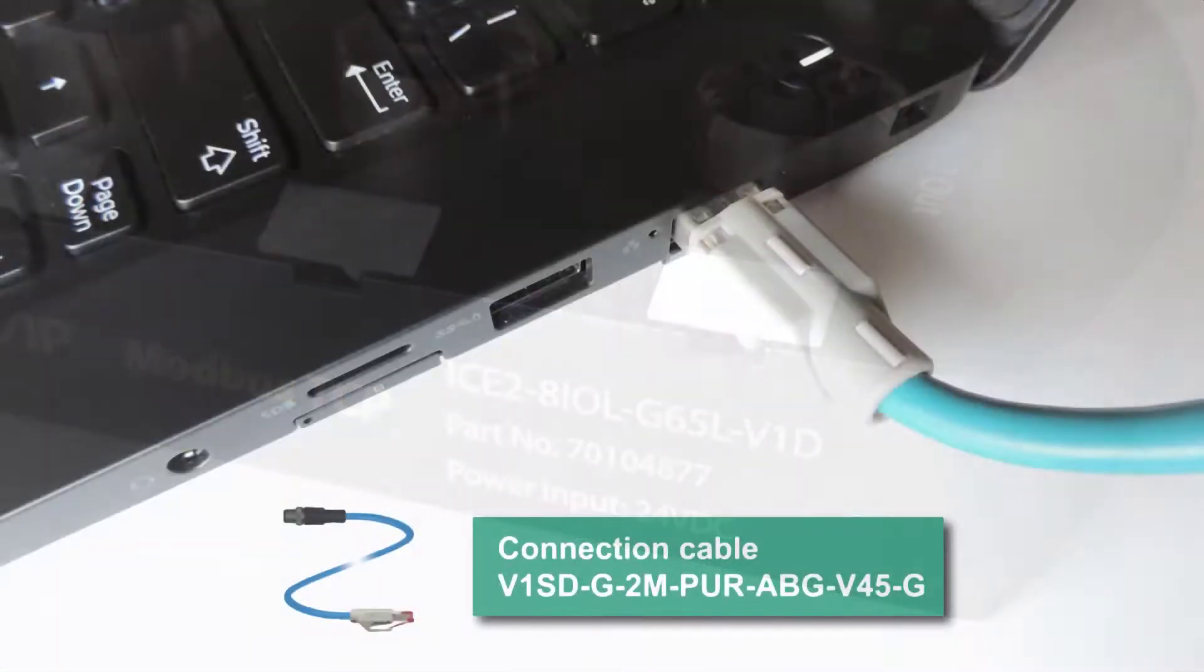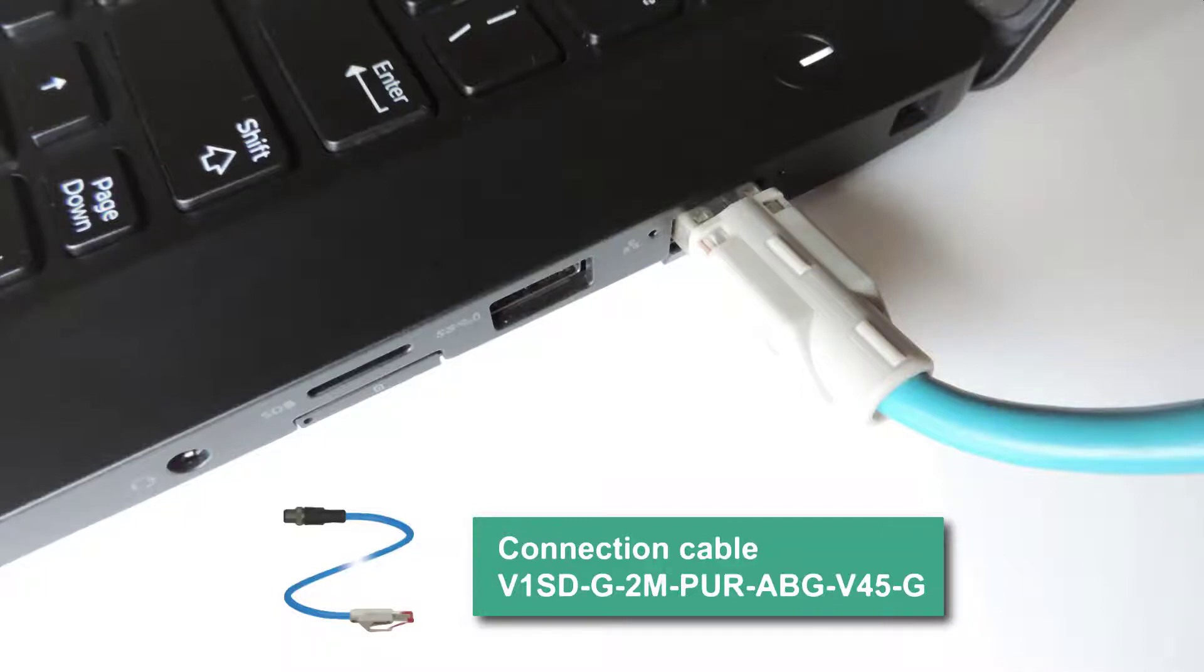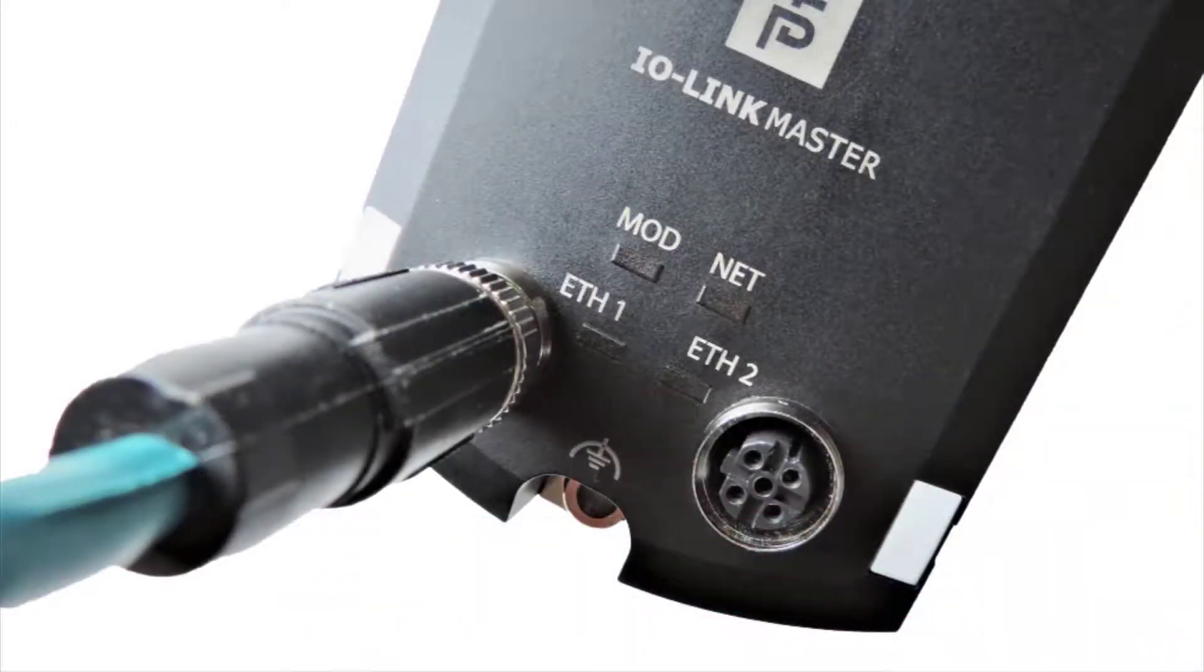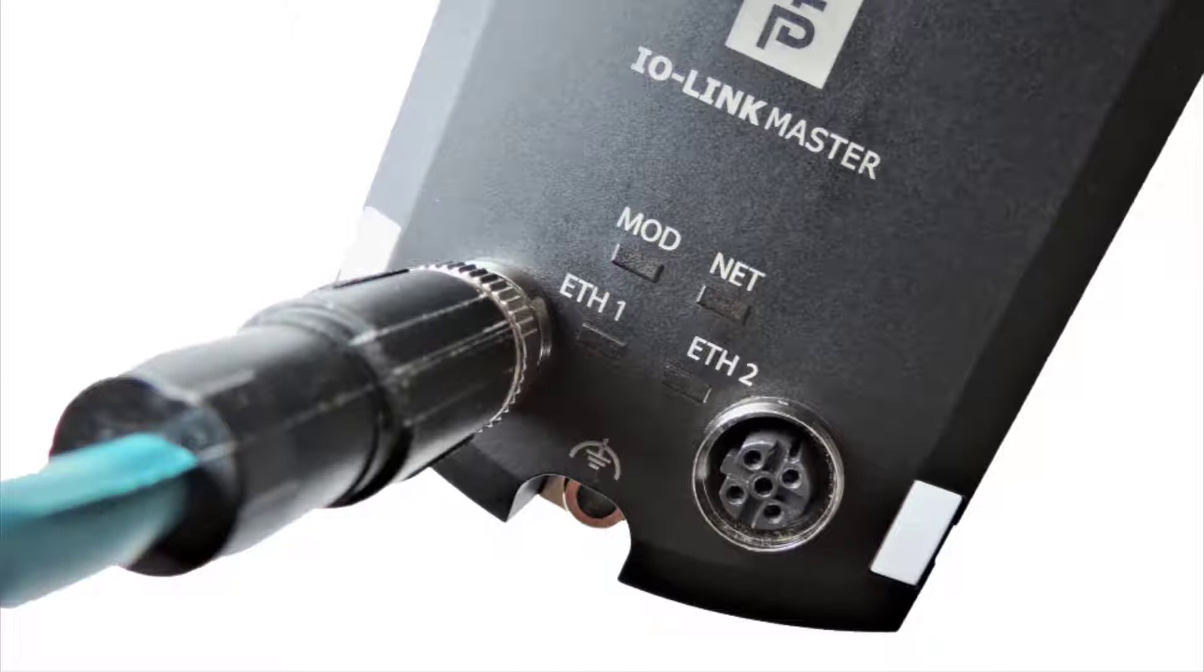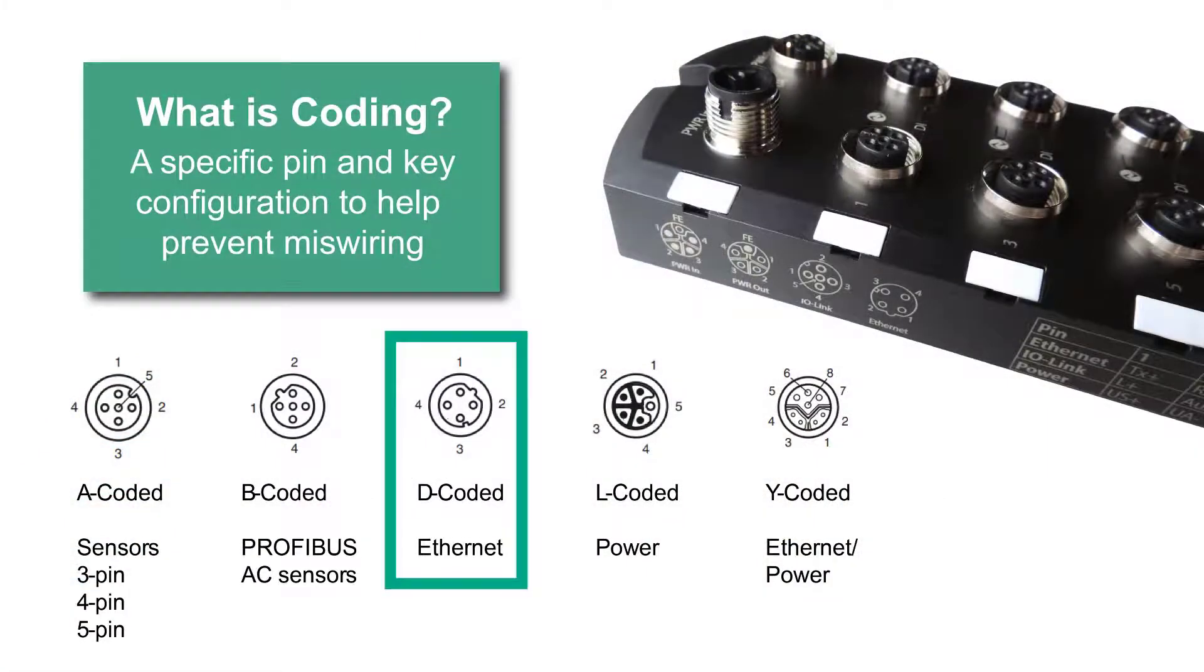I'm going to hook up the ICE2 block to the laptop's Ethernet port using a D-coded connection cable. Shown on the screen is the cable that I'm using. Depending on what you're doing, instead of a laptop, maybe you connect this cord to an Ethernet switch or a PLC. I'm going to connect to Ethernet port 1 at the bottom of the ICE2 block. You can see that there are two Ethernet ports which allow for daisy chaining if the application calls for it. A connector cap should be added to the unused Ethernet port to keep out fluid and dust. D-coding is shown here in the middle. Notice it's used for Ethernet.